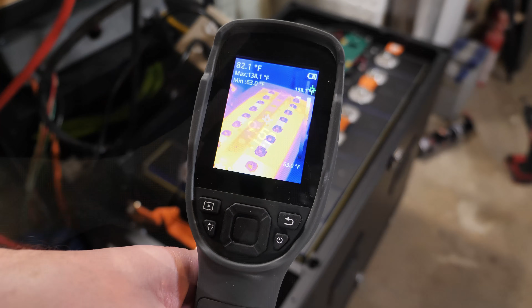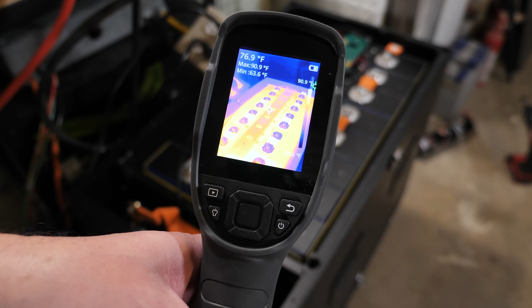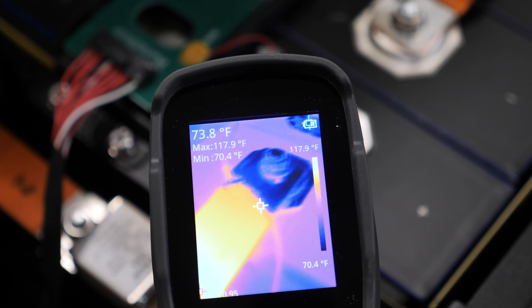All right, time now is 9:52, we're almost at 10 minutes. Let's go ahead and take a temperature reading. Just over the center of the pack, it's showing 77 degrees Fahrenheit, but I'll bring it in a little closer and read them off to you. Cell 16 right on top is 83, 84 degrees. If I go to the bus bar, showing 112.